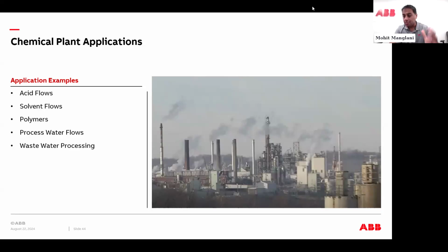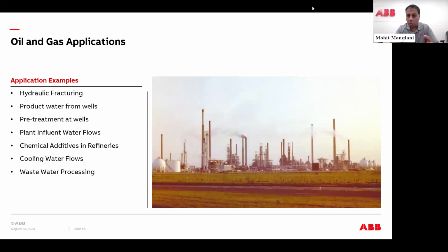You think of paint. Paint is not the best application for a mag meter because number one, it coats. Number two, it may not be conductive. Process water and wastewater processing, obviously on the industrial water side for chemical plants. Oil and gas applications, obviously on a separator, probably have oil going one way. You'll have the water that's being fractured out going another way. Typically in our space, we see mag meters on the water side, and on the oil side, we'll see Coriolis meters. Another technology, just to kind of give an example.